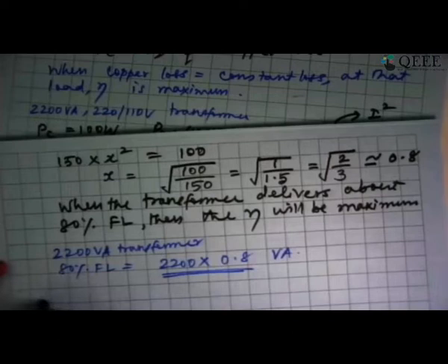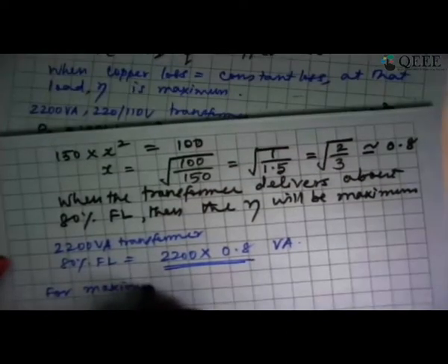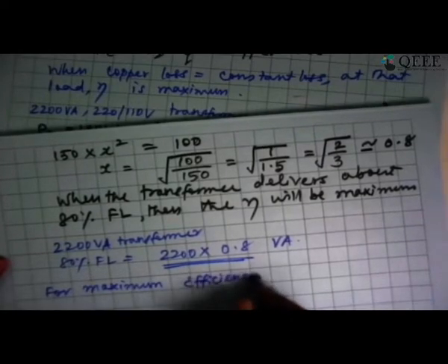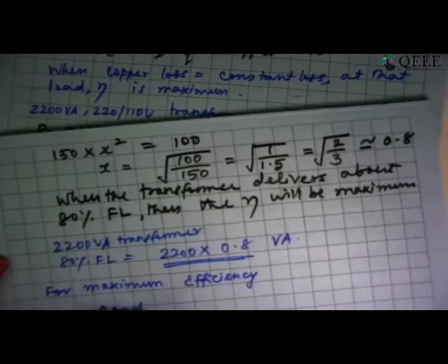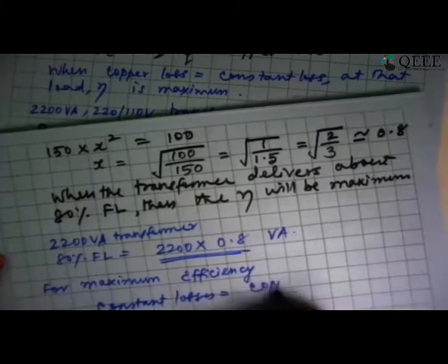Let me reiterate, for maximum efficiency, constant losses should be equal to the copper loss at that load.